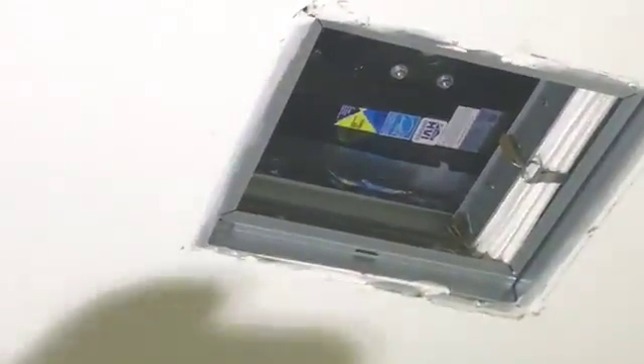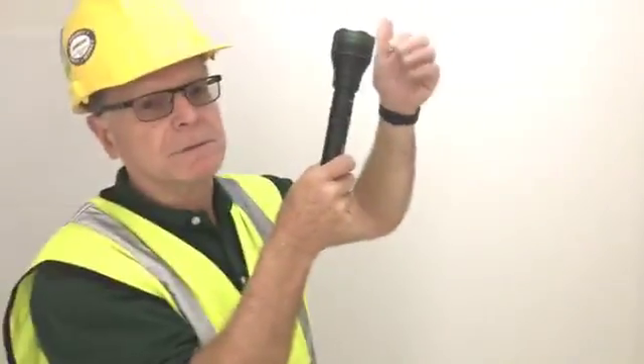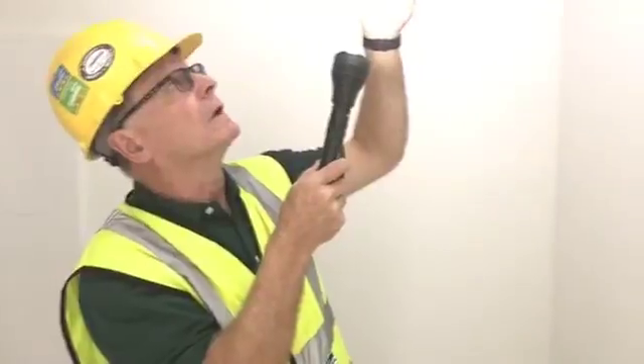On this bathroom fan, we have radiation dampers, which is not very typical in what we've seen builds in this area, but they have sealed the drywall around it. They've also sealed, if you could take a look, we found some air leakage through the slots in the housing, and that was fixed. So again, we're trying to get our target 50 CFM intermittent, and we also have a continuous flow rate, which meets LEED and Energy Star, which is part of version 4 for these units.